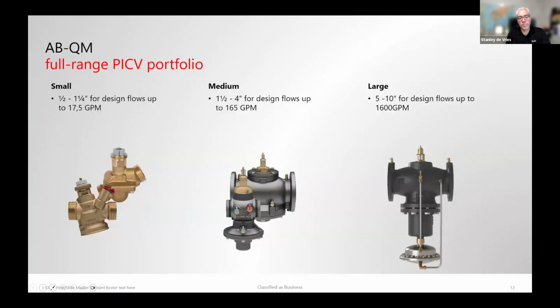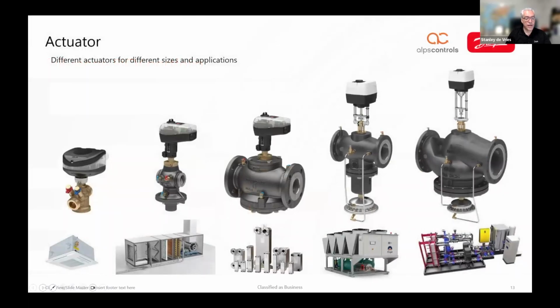So what is the portfolio that we have? Well, we go from 1/2 inch to 10 inch, from basically 0 to 1,600 gallons per minute. For most normal HVAC applications and buildings, you would usually stick to the 4 inch, which covers many buildings, but we do have bigger ones. Specifically in, for example, Dubai, where they have a lot of district energy and district cooling, these are also quite popular. So there is a big range, and obviously we also have actuators that fit on that. 0 to 10 volt, 4 to 20 milliamps, that's all available.